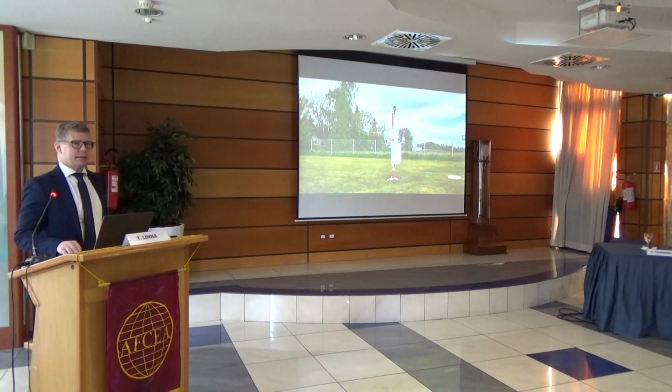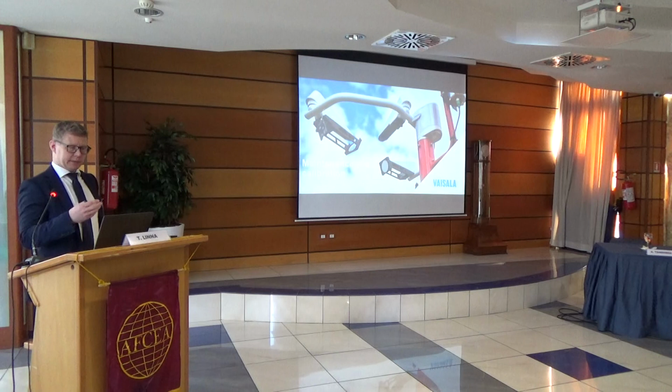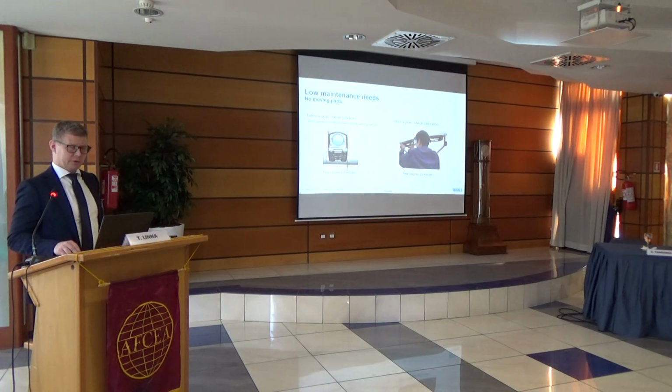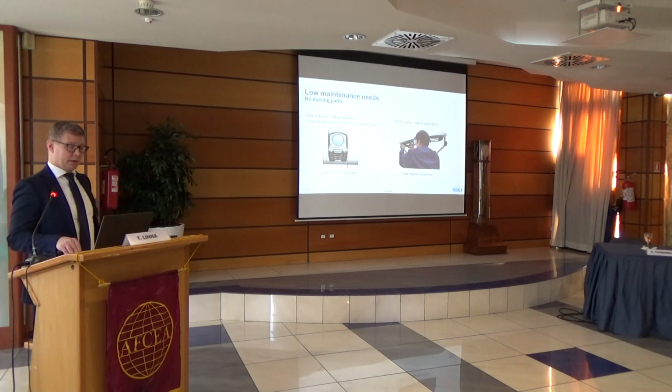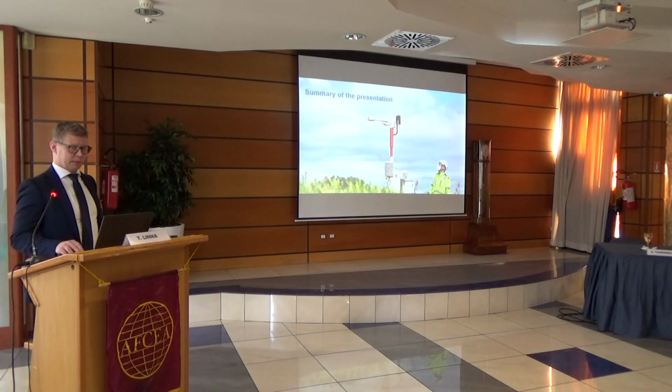Readily calibrated and ready to go. Just fire it up and initiate the software, enter the codes and have the sensor be there. So basically only twice a year cleaning windows. In some extreme cases one needs to clean them more often and then maybe checking the calibration once a year. In practice the calibration does not drift, but checking the calibration is for like a security preventive measure.